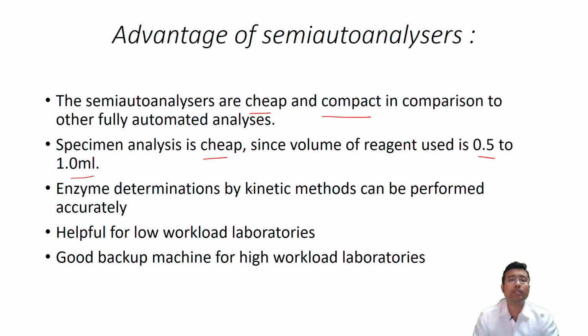Next, enzyme determination by kinetic method can be done accurately. If you are doing it in a colorimeter, you need to manually measure all the time-based assays, but in the case of semi-auto it will just do it for you. Next, it is very helpful for low workload labs, because for high workload labs, or the labs which have an automated analyzer, you need highly skilled or trained technicians to operate the auto analyzer because there is much more complex programming involved in that.